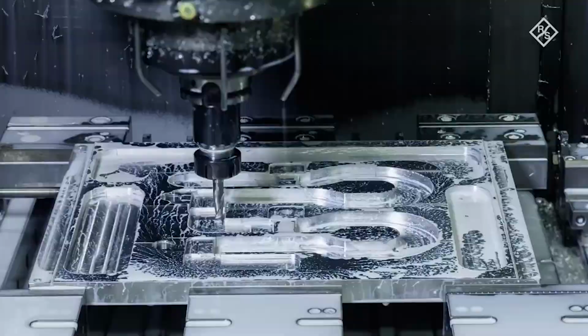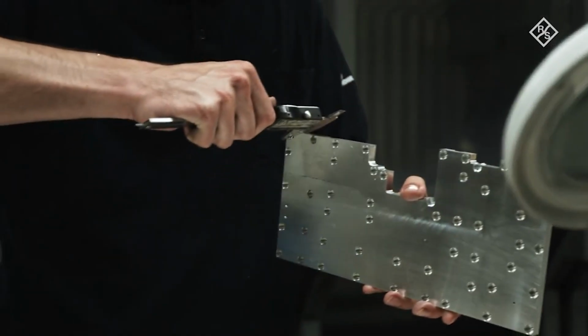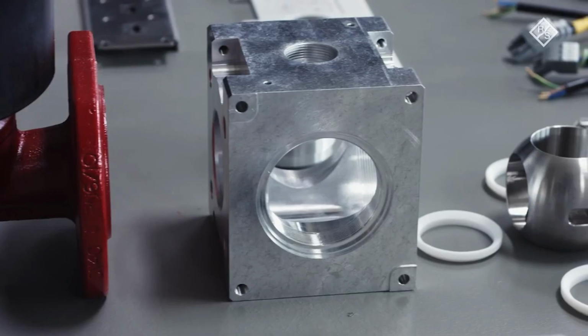A properly designed system cools every heat-generating component, including the power supply, directly through a custom-engineered cooling plate, which provides a very stable temperature for all heat-dissipating components, reducing stress and extending lifetime. With no airflow passing over sensitive electronics, environmental contaminants like dust, salt, and insects simply never become an issue. The result is stable operation, lower room heat, and a dramatically reduced AC load. Also, the transmitter is not dependent on the HVAC system in the room.